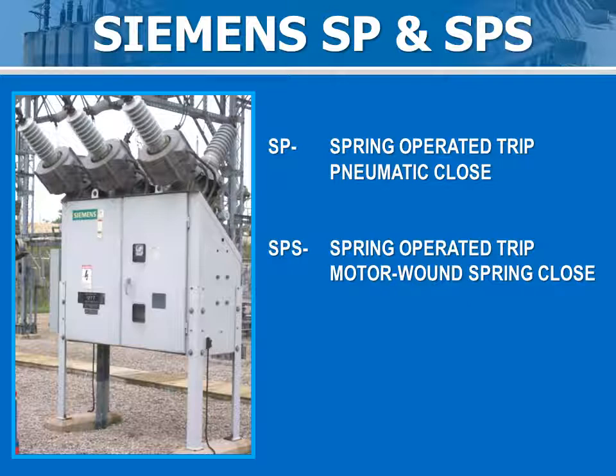The basic difference between the SP and the SPS is the closing mechanism. The SP uses an air ram to close the breaker and at the same time charging the trip spring. The trip is accomplished by releasing the trip spring. The SPS uses a motor wound spring mechanism for closing and charging the trip spring. Again, the trip is accomplished by releasing the trip spring. Both breaker models are rated for 3-cycle operation.